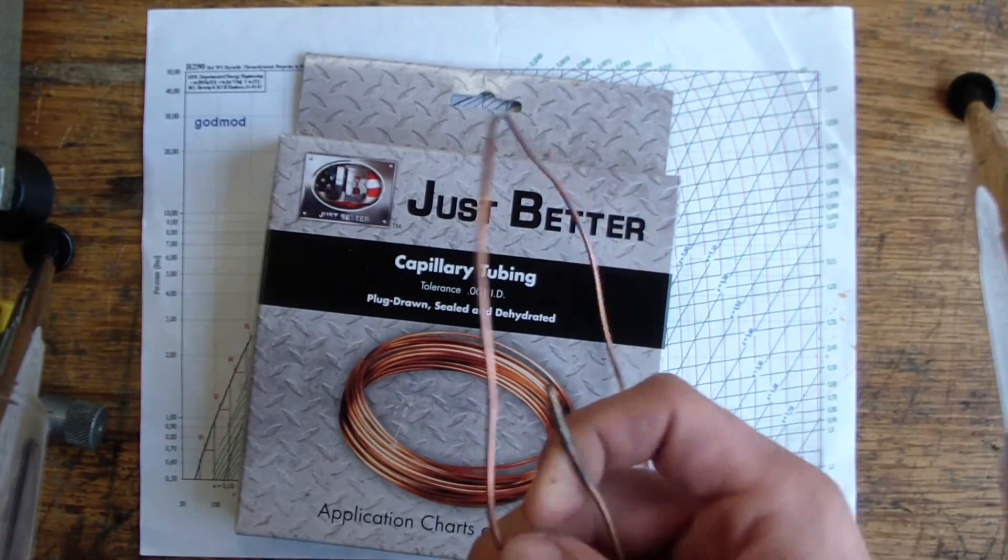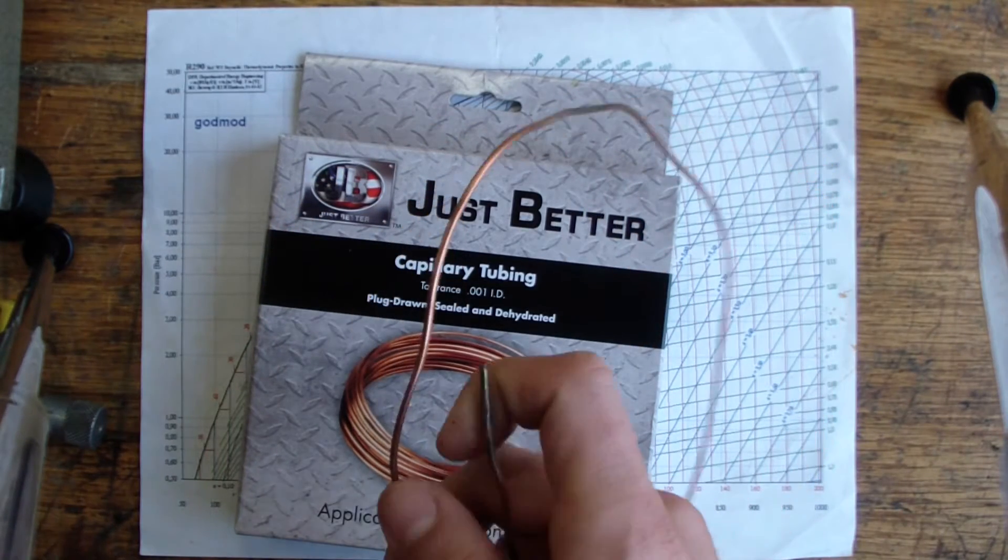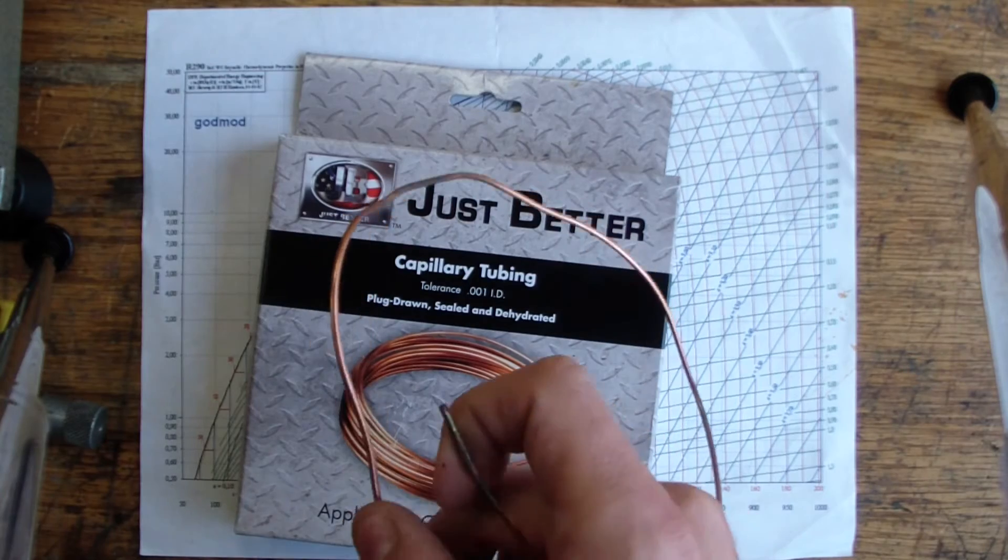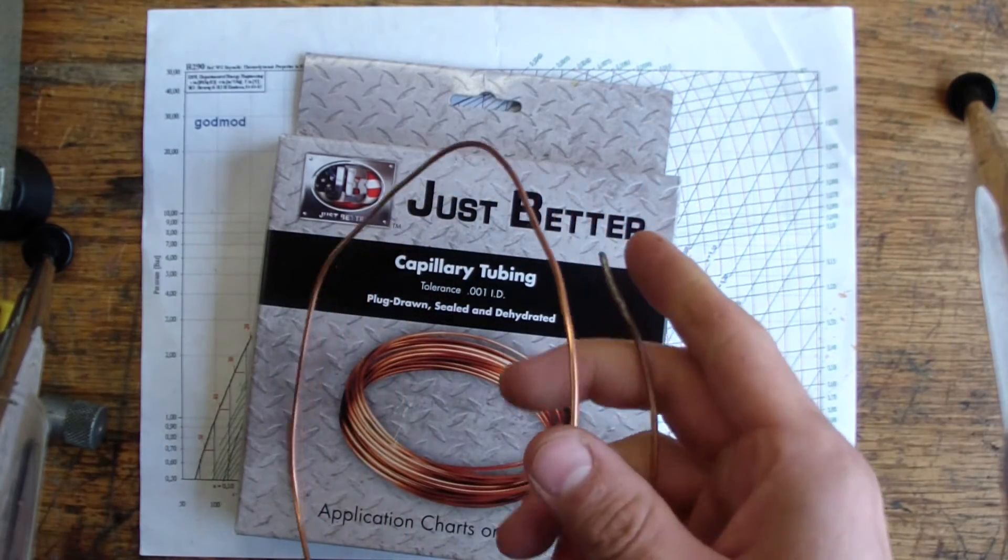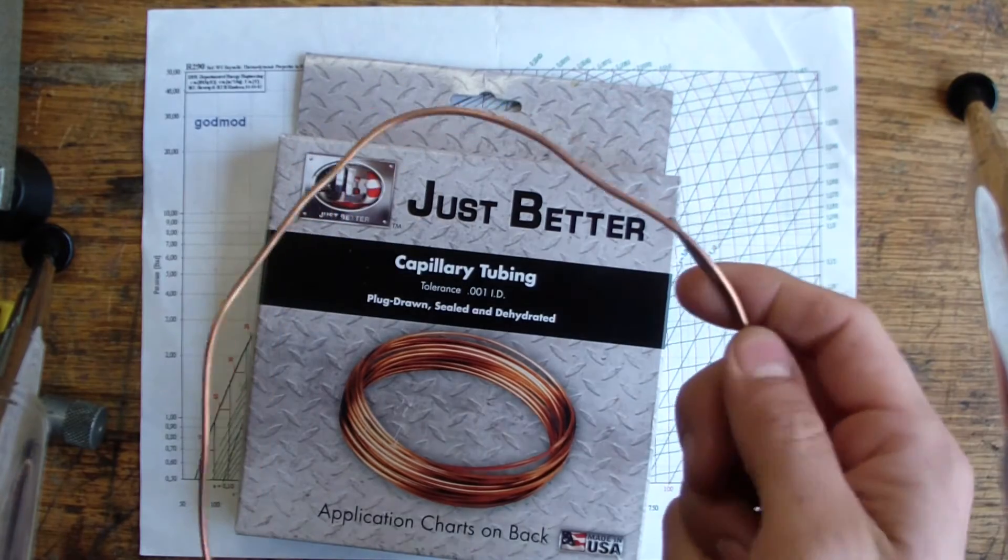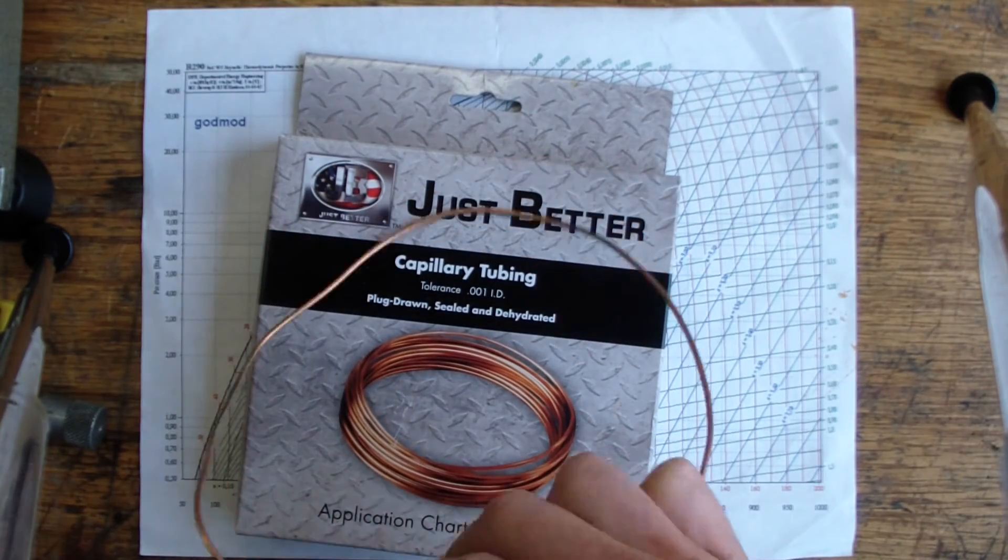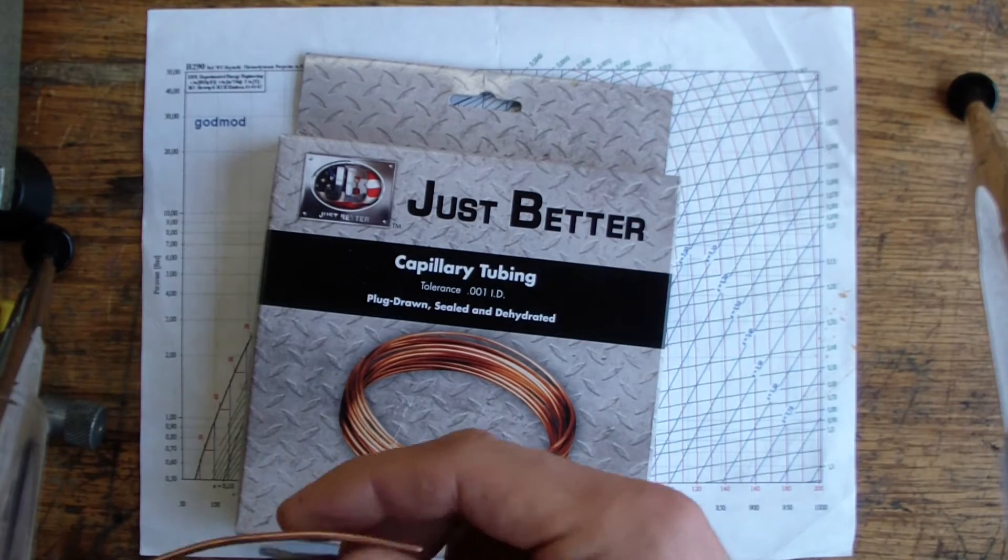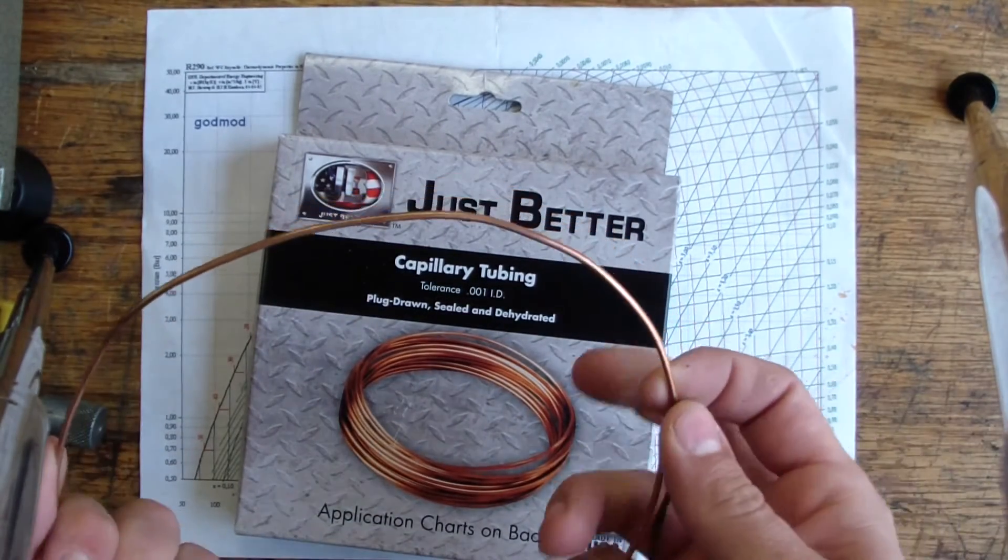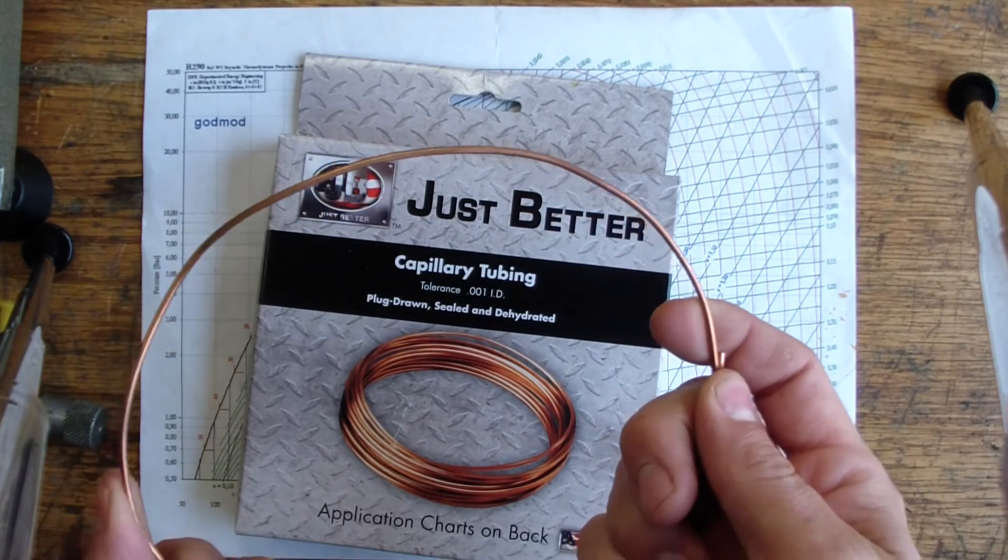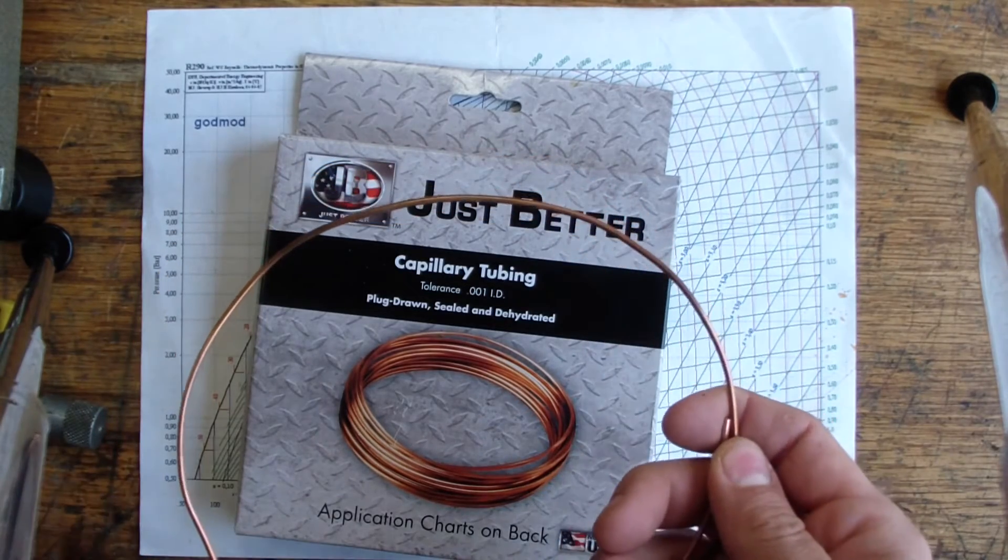And unlike a fixed orifice, which doesn't have no way to regulate refrigerant flow through it and the conditions, the capillary tube can do that to a certain extent. Capillary tube can maintain a liquid plug before it in a relatively wide range of ambient conditions, unlike a fixed orifice.